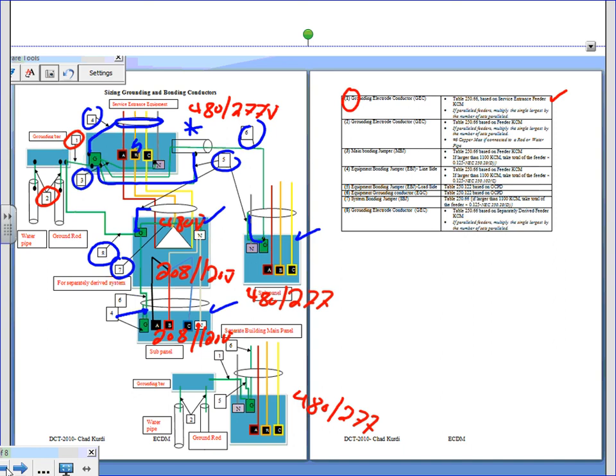Any question, guys, about this? Okay, number 8, I want to bring to your attention that number 8 is the grounding electrode conductor. Grounding electrode conductor, number 8, guys, is the grounding electrode conductor for the separately derived system. The only reason why I called it number 8, Brooks, is because it is a grounding electrode system for the separately derived. The same calculation.